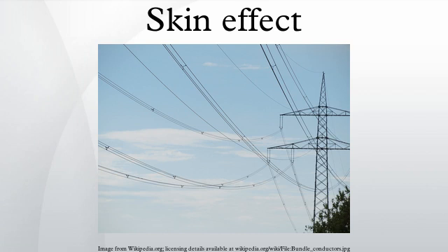High voltage, high current overhead power lines often use aluminum cable with a steel reinforcing core. The higher resistance of the steel core is of no consequence since it is located far below the skin depth where essentially no AC current flows. In other applications where high currents flow, solid conductors are usually replaced by tubes, completely dispensing with the inner portion of the conductor where little current flows. This hardly affects the AC resistance but considerably reduces the weight of the conductor. The high strength but low weight of tubes substantially increases span capability.